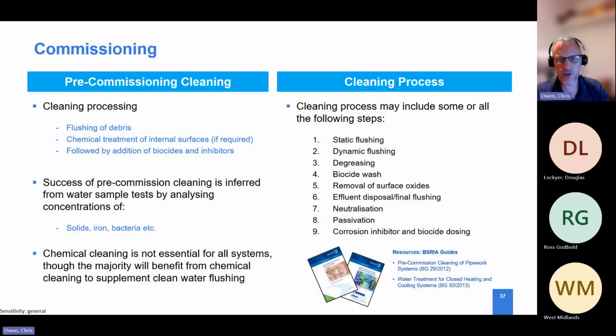And again, commissioning can be a CPD in its own right, quite a complicated, complex subject. However, we know that most of the processes involve some sort of flushing out of the debris, which is good because debris, as we've seen, can cause corrosion mechanisms. The chemical treatment of the internal surfaces as part of a cleaning process can be quite beneficial in terms of removing any debris or internal scale which can contribute.